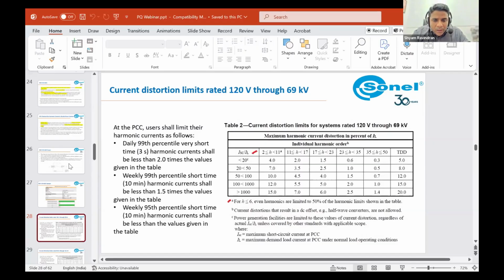With more and more RE and ESS coming into the picture to make the grid greener, even power generators could be a source of harmonics with poor power quality. Although the grid code compliance requirement at PCC is supposed to be compliant with 519, do you observe scenarios where RE plants and PCS are contributing to power quality and harmonic exceedances?